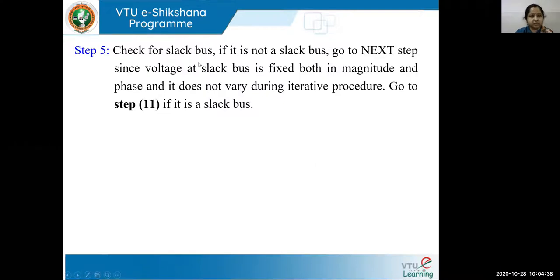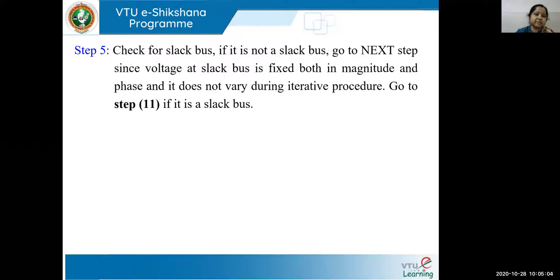Inside the iteration loop, after setting the bus count, if it is not a slack bus, go to the next step. Since the slack bus voltage is fixed both in magnitude and phase, and it does not vary during the iterative procedure, go to step number 11 if it is a slack bus. Step number 11 will increment the bus count: P = P + 1. If it is not a slack bus, proceed to the next step.